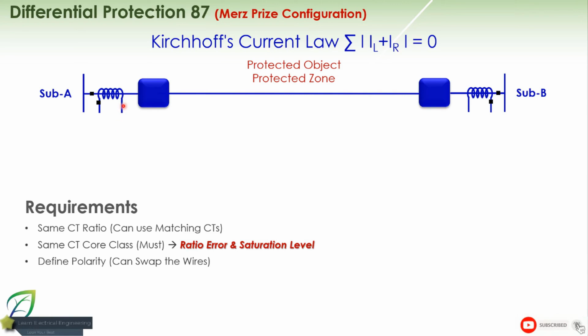Okay, here when you say 1% and here also 1%, this value is somewhat large. Now, if we take another class like the PX class, it is the customized protection core where you provide all your specifications. The important thing is that it tells you it will not exceed plus or minus 0.25%, which is very nice.